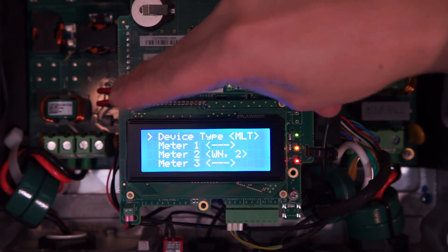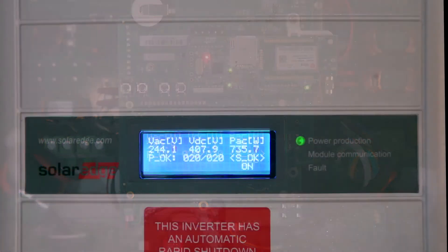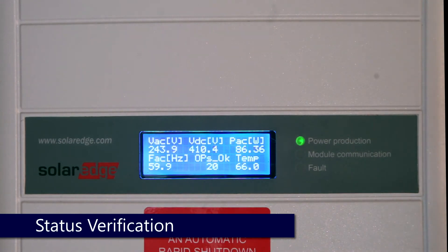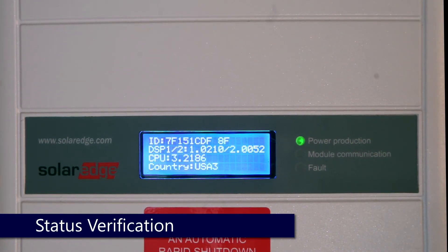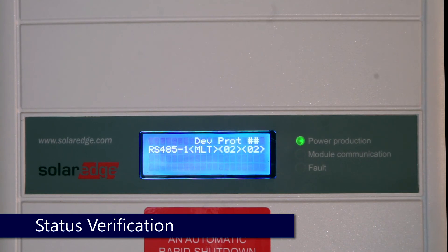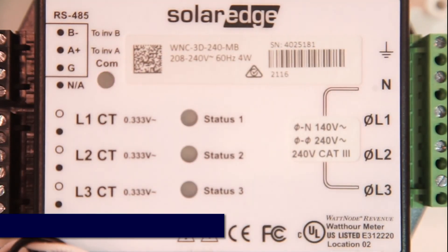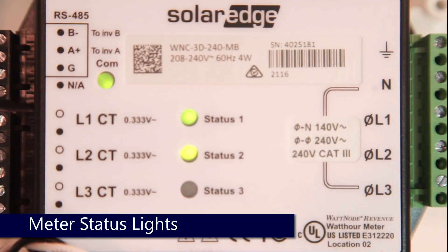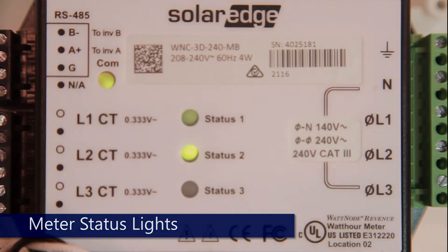Then go to the import and export meter status screens to verify all measurements are correct. To scroll through the status screens, just tap the green button underneath the screen. Verify everything checks out and that we've got OKs on both meters. Then verify on your meter itself that the CT lights are blinking green and that we've got a green meter comms light. Thanks for joining us in the SolarEdge Learning Lab.